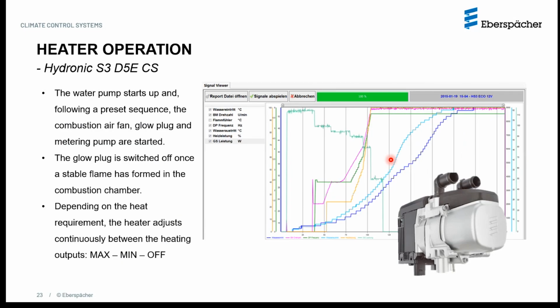So this slide shows us the actual operation of the Hydronic S3 heater. Along similar lines, it will also do a systems check initially. If it passes the test, then the coolant pump starts, goes through a set of preset sequences where the fan starts, the glow pin starts, and the fuel pump is then eventually started, supplying fuel to the heater. The glow pin will be switched off once the flame is detected.